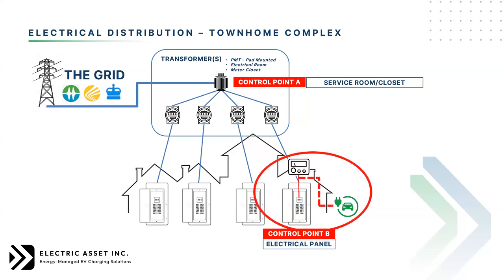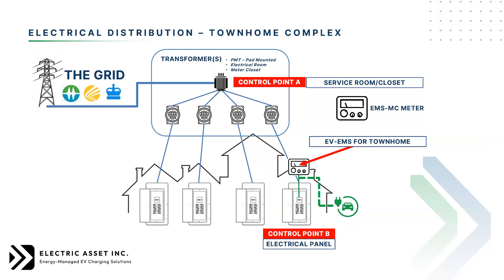In a townhome, one solution, much like a residential condo, is to put in a metered service, an EMS controller, which monitors the demand on that panel in real time and controls the charger and level of charge going to it. During peaks in usage of all electrical loads in the townhome, the EMS will throttle the charger down accordingly, ensuring the electrical panel never exceeds its recommended capacity. The other control point would be the service room or the EMS meter center controller.